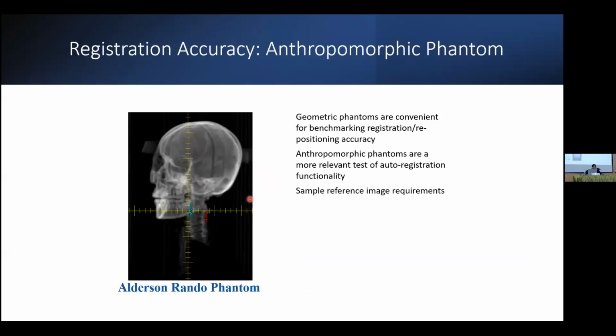This one I want to point out is a phantom that I think would be helpful: an anthropomorphic phantom. If you're doing this with a Varian TrueBeam, let's say, there are 1,000 of them that exist, so you could go somewhere else and see how that one performed. The registration system, whatever company you're going with, they have to write software code to do the registration. How well did they write that code? How well does it perform for different anatomical sites? Sometimes, and this has happened before, they write the code very well and it works really well on the phantom they used and is horrible with anything else.